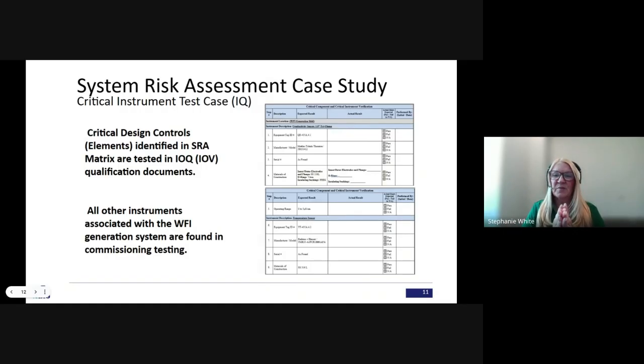So an auditor would be able to take a user requirement—a quality requirement—and open up the system risk assessment and see that this quality requirement maps to these critical elements, these critical alarms, and then we pull that information forward into an IOQ. You can literally follow the bouncing ball, or trace it, from user requirement to system risk assessment to protocol. Then of course you'd have your trace matrix at the end, but you can see that all the elements we deem critical, or quality critical, appear in our protocols.